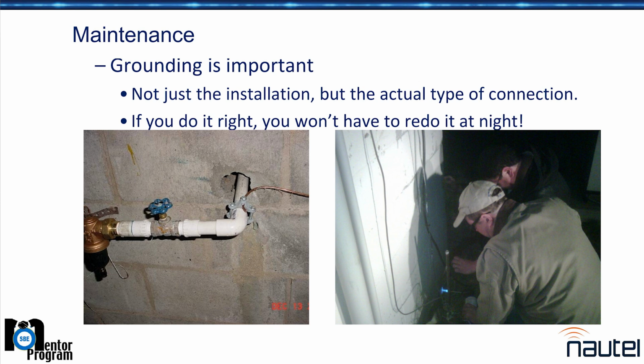One on the right, station owner, Arkansas. Like I said, some of my best stories come from Arkansas. He's brazing a ground connection, and this comes back to a question that I got asked in an email recently, and we'll get to that in a second. But he's brazing the 2-gauge copper wire that's coming out of the building to the ground rod, and he's doing this at 9 p.m. by the light of the Jeeps, because I had walked through on an inspection about 15 minutes before, reached down and stood up holding the wire in my hand.